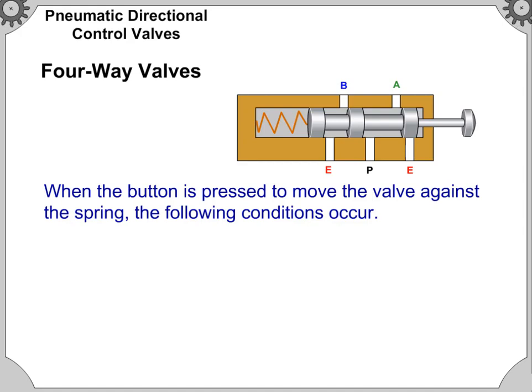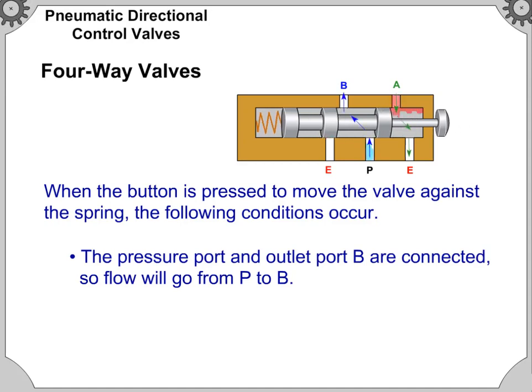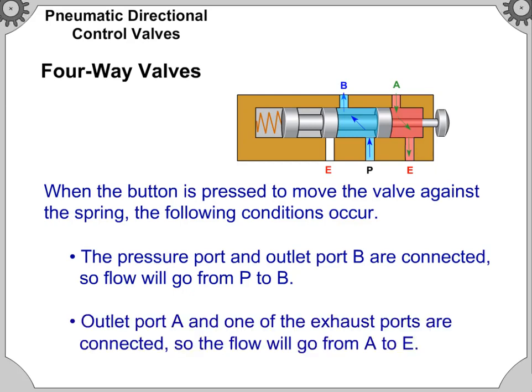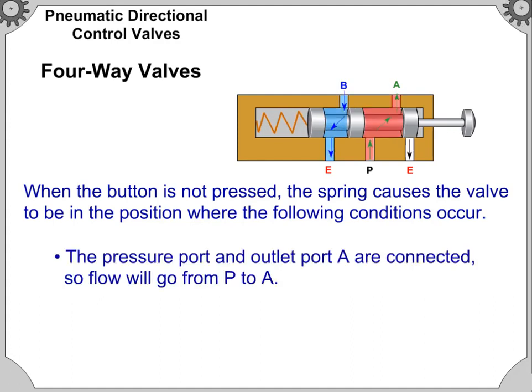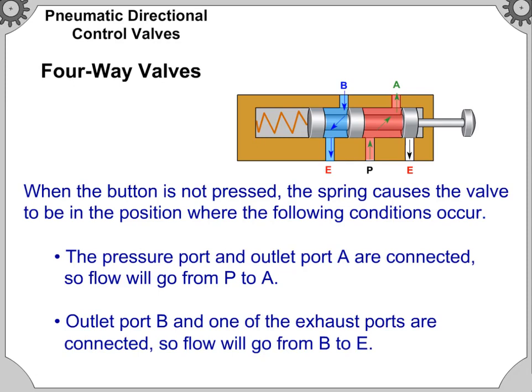When the button is pressed to move the valve against the spring, the following conditions occur: the pressure port and outlet port B are connected so flow will go from P to B, and outlet port A and one of the exhaust ports are connected so flow will go from A to E. When the button is not pressed, the spring causes the valve to be in the position where the pressure port and outlet port A are connected so flow will go from P to A, and outlet port B and one of the exhaust ports are connected so flow will go from B to E.